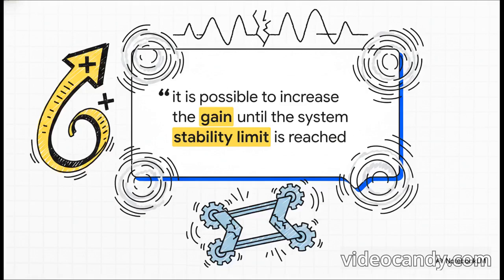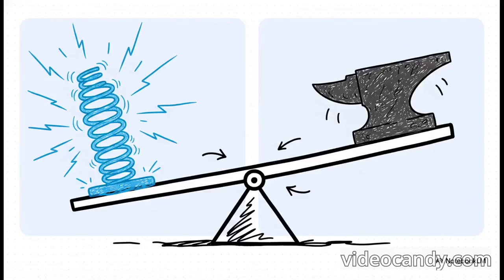Finally, Section 4, Stability Secrets for Nonlinear Inductive Loads. So, we fixed the digital side, but as we push our proportional gains to the absolute maximum to aggressively reject physical disturbances, we slam right into physical reality, the mechanical resonance limits of the machine. The physical frame itself begins to flex. If you've ever been on a factory floor and heard a servo motor suddenly start shrieking, this is exactly why. Pushing the gain too far causes the motor to make aggressive noise, and the mechanical load violently oscillates.